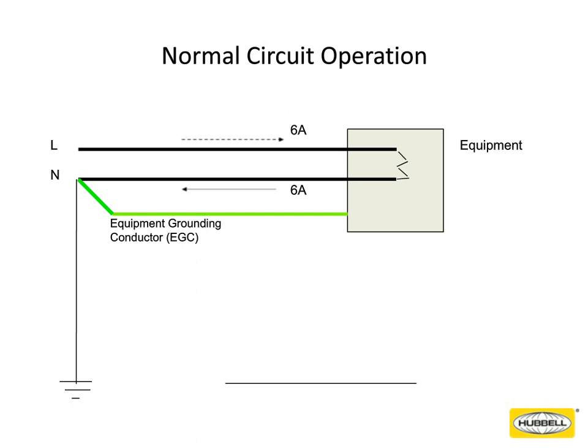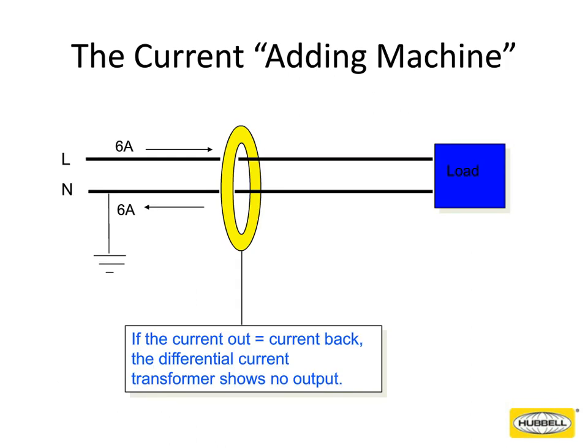In a normal circuit, you have a line in and a neutral. You have current coming in, current coming out to complete the circuit. Common sense, right? Well, in this particular illustration, we have 6 amps coming in and 6 amps coming out. That is your normal standard circuit. Whatever the load is, that could be 8 amps, 9 amps, 10 amps, whatever you have coming in on the line, you're coming through the load and you're coming back on the neutral, they should be in balance. A ground fault basically monitors those circuits and checks that the current coming out is equal to the current coming back. So if you have 6 amps coming into the load, you better have 6 amps coming back.